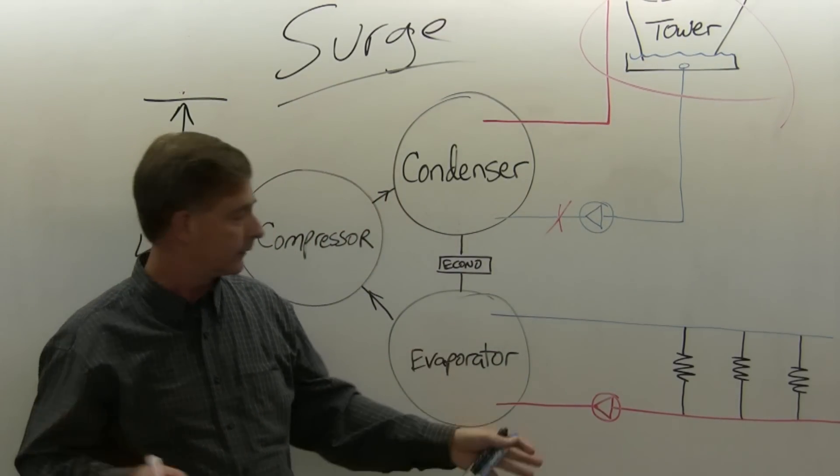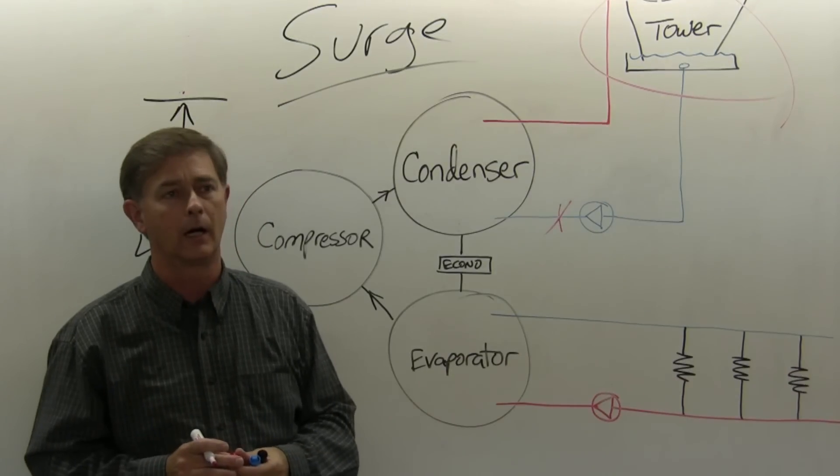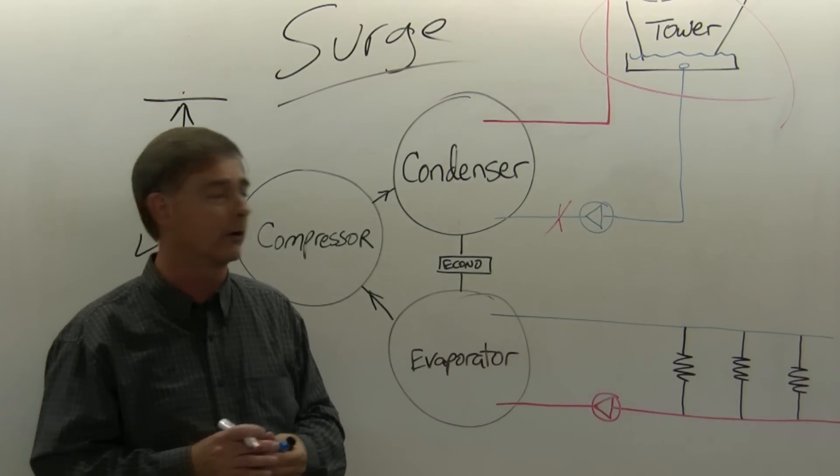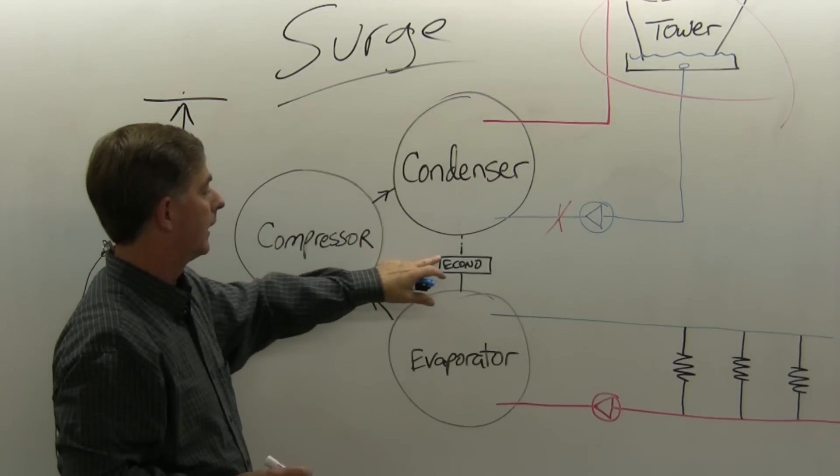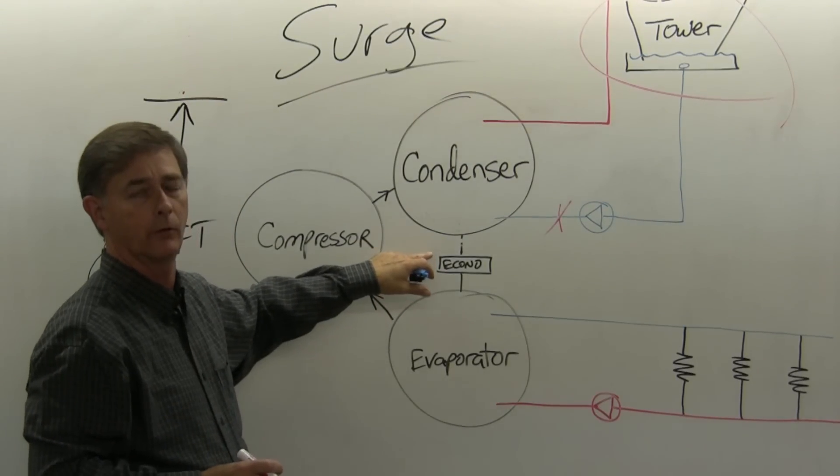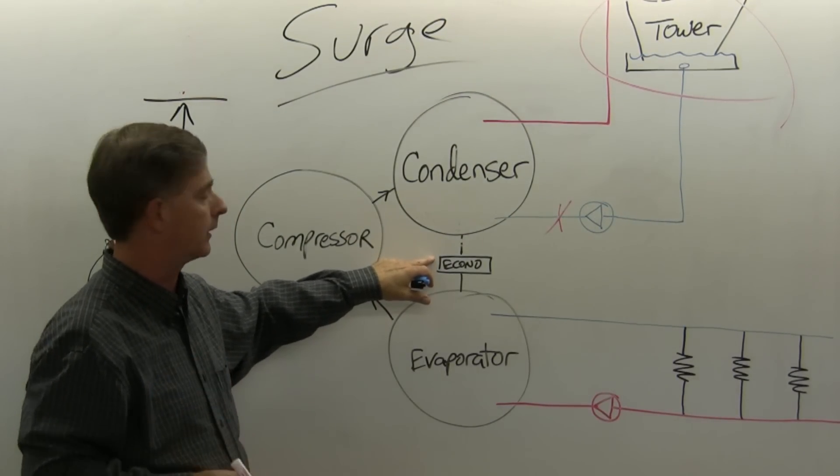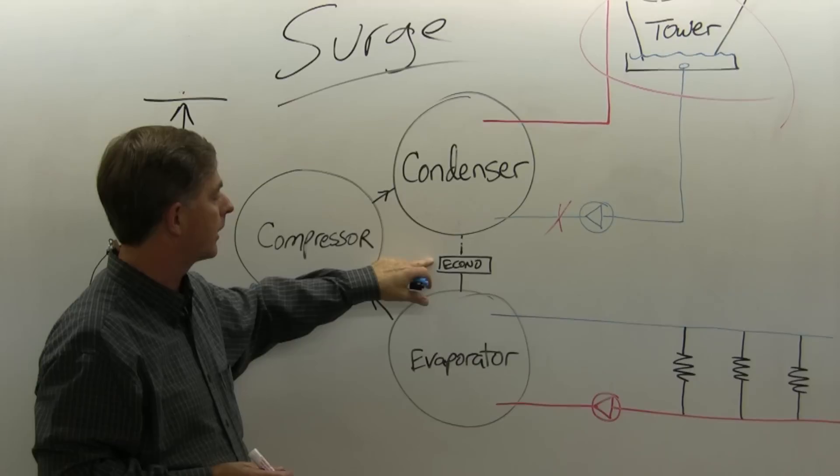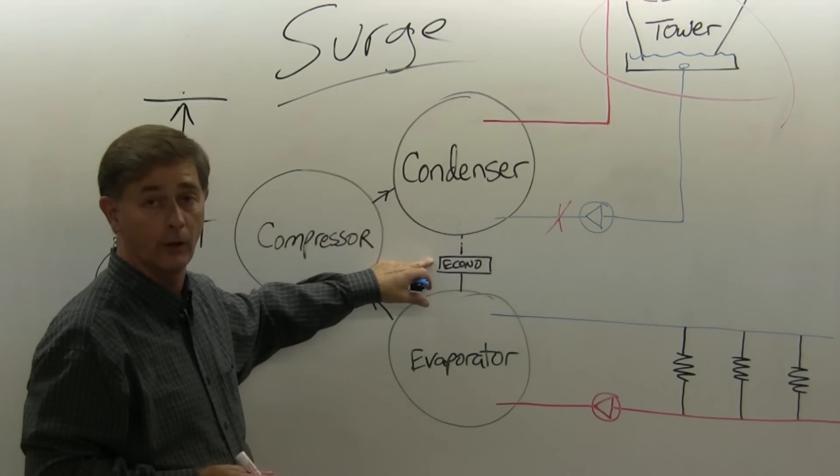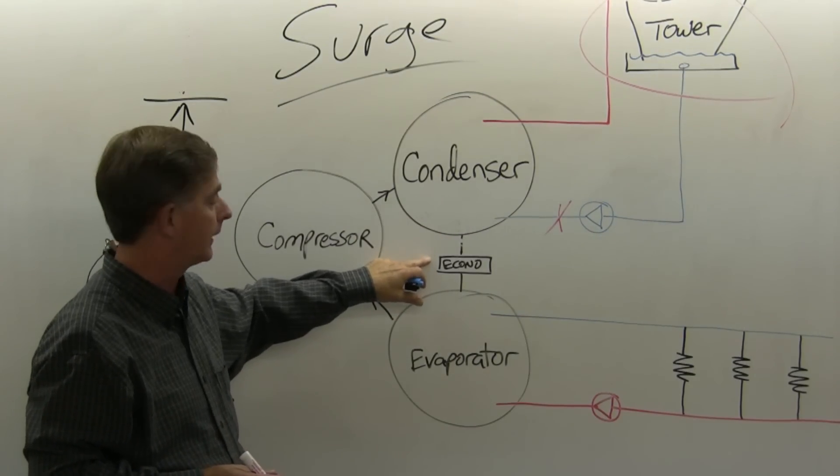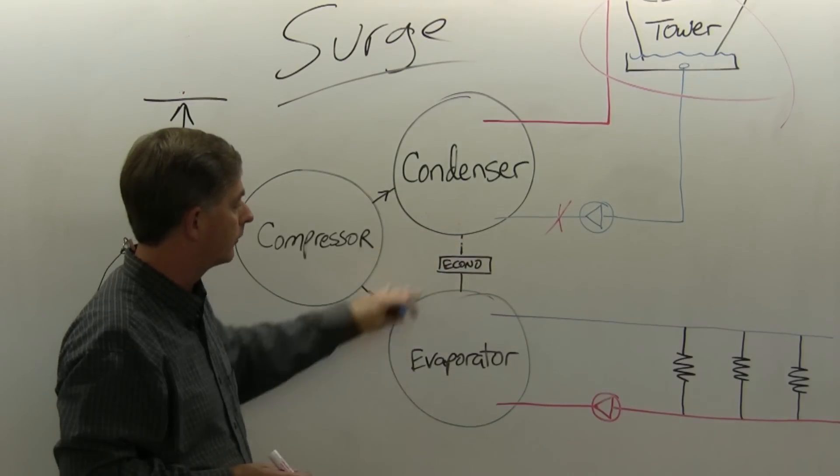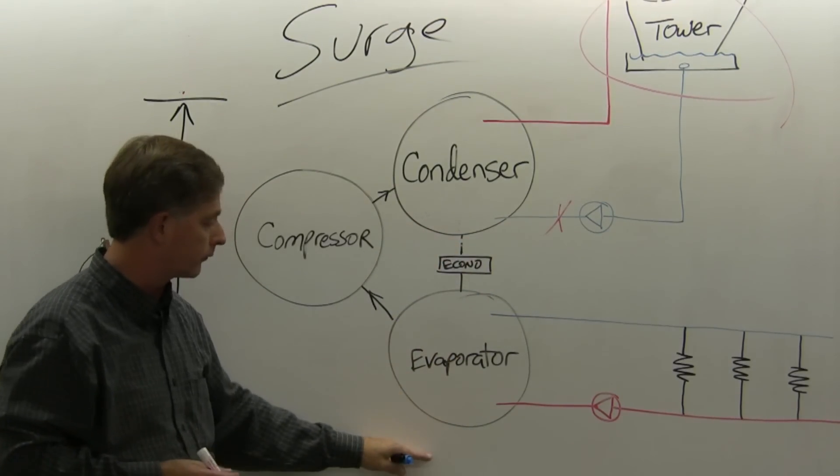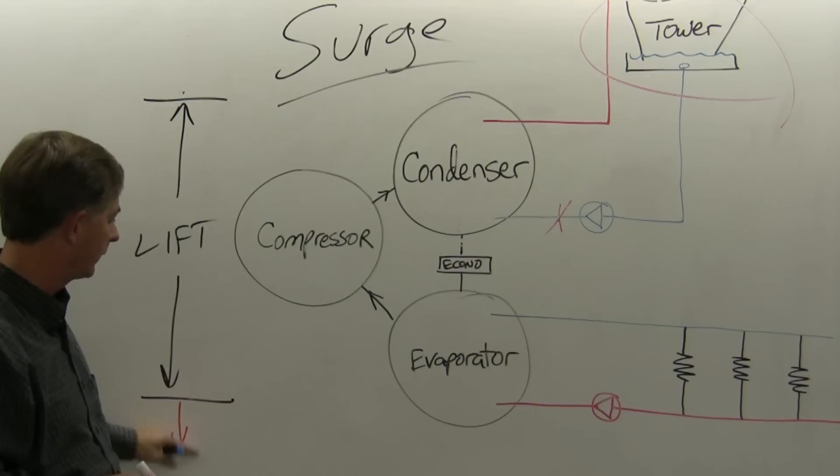You can have a stopped up strainer, low refrigerant charge. You might have a little issue going on if you have an economizer with an orifice that's starting to get contaminated and stopped up. If you have a float, if your machine has a float and it starts sticking, that can also lead to the low side pressure dropping, temperature dropping, and leading to surge.